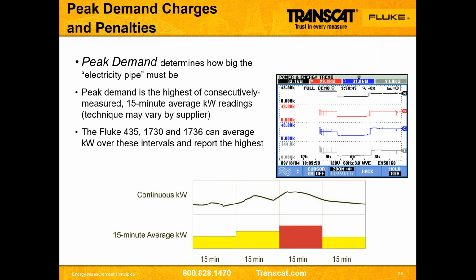So the peak demand piece that we talked about earlier really comes into play. Every 15-minute interval, the utility is out giving you a snapshot of how much you're using. If they establish a number, and let's say we use 1 gigawatt worth of power a month, and you use 1.1 gigawatt at one point in time during that month, they will hit you with what's called a peak demand charge. And that will actually apply for the rest of the billing cycle.